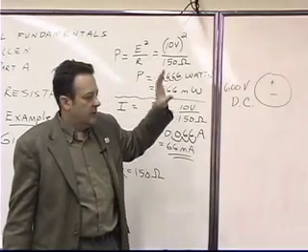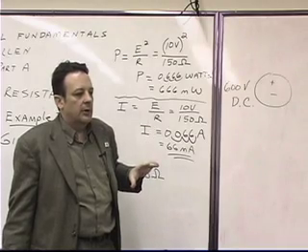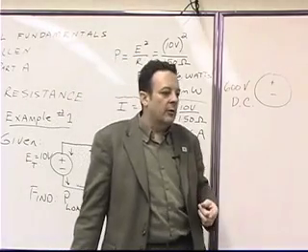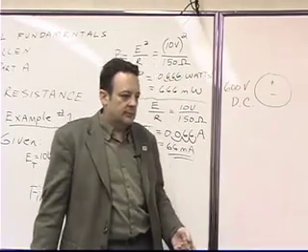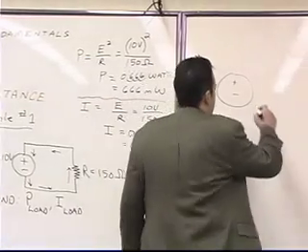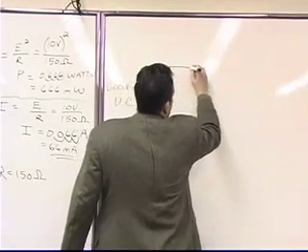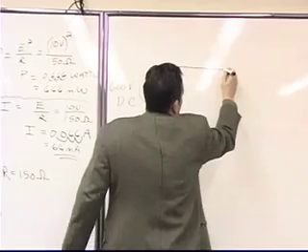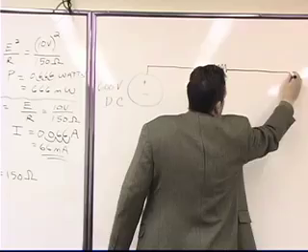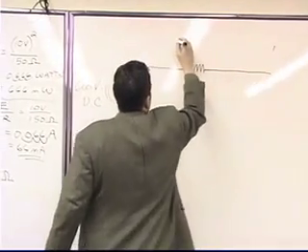Right, but in this particular example, I'm just showing an example where we're not going to do that. We're not going to convert it to AC, and the reason is because the pump motor that we have runs off DC. And you can buy pump motors that run off DC. So this is a long stretch. This piece of wire stretches a long way, and as a result, it's got some resistance in it. Because if we actually measure this distance right here, this is 2 miles.